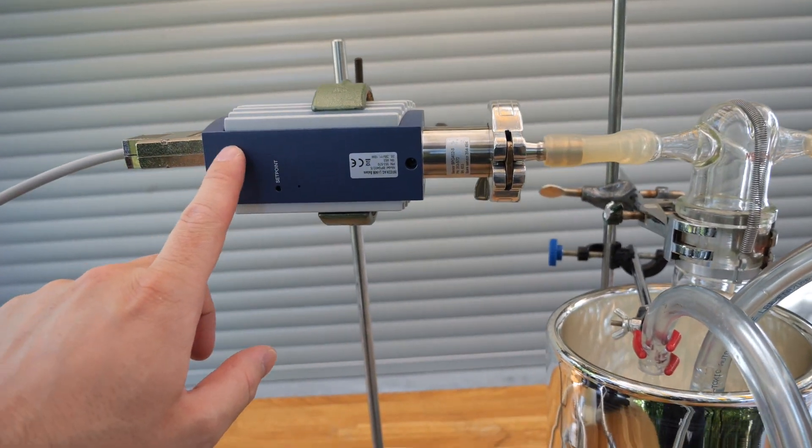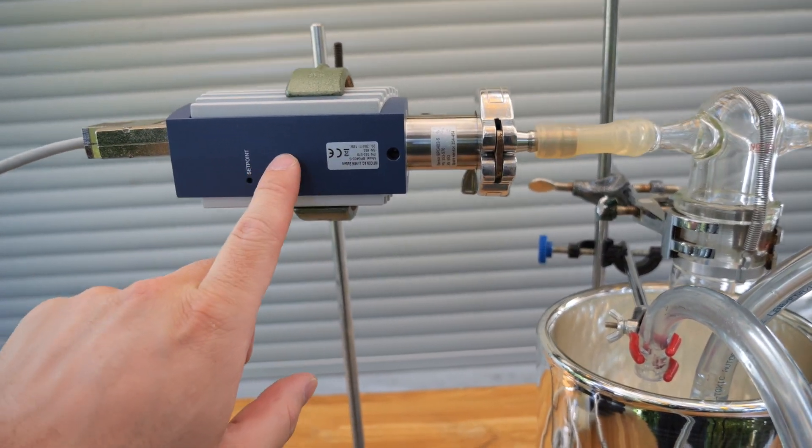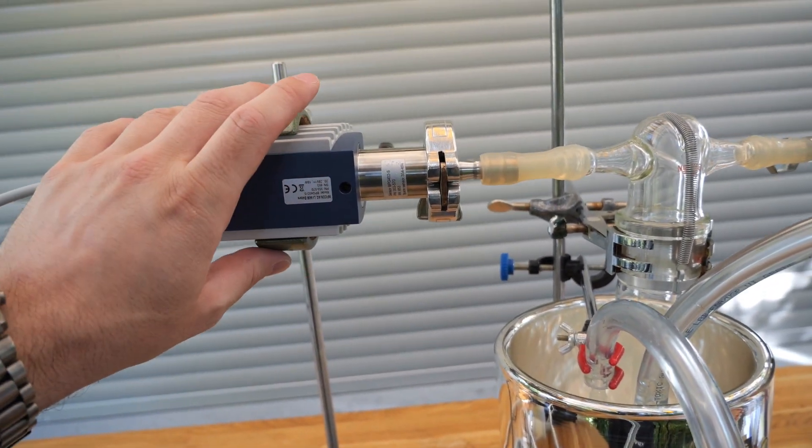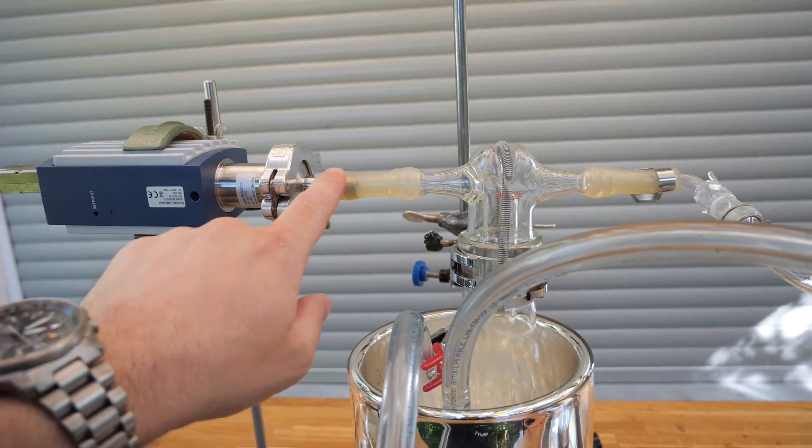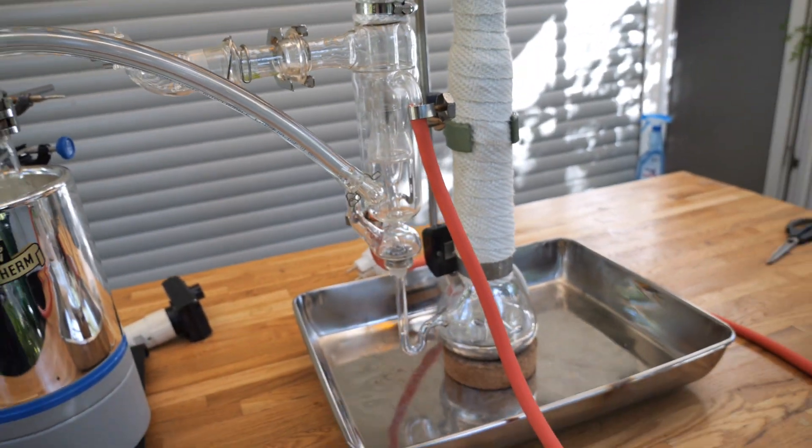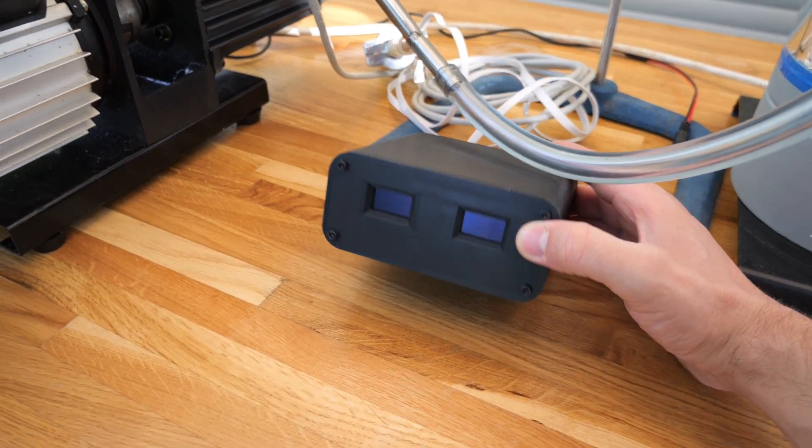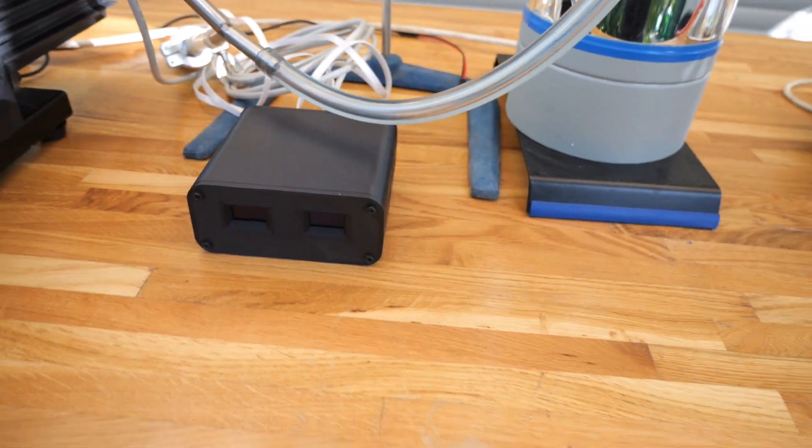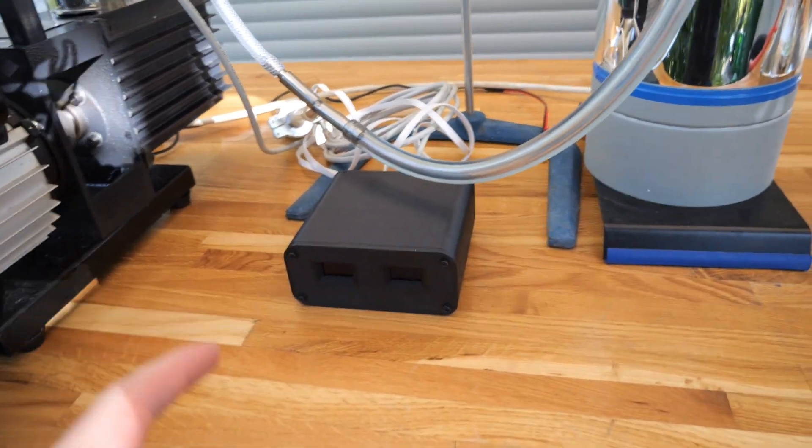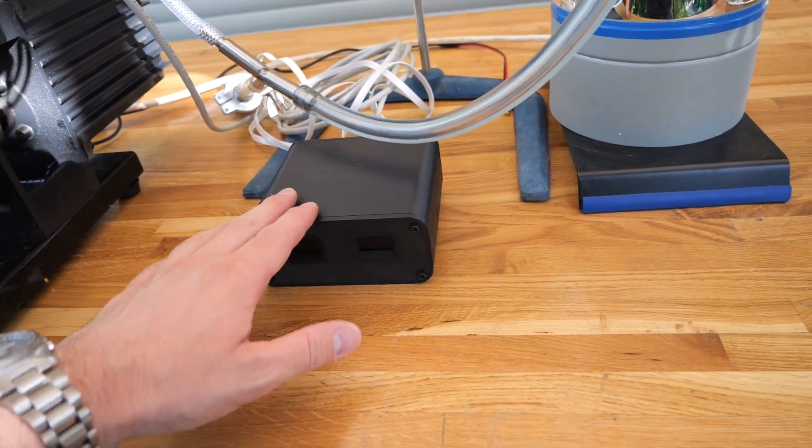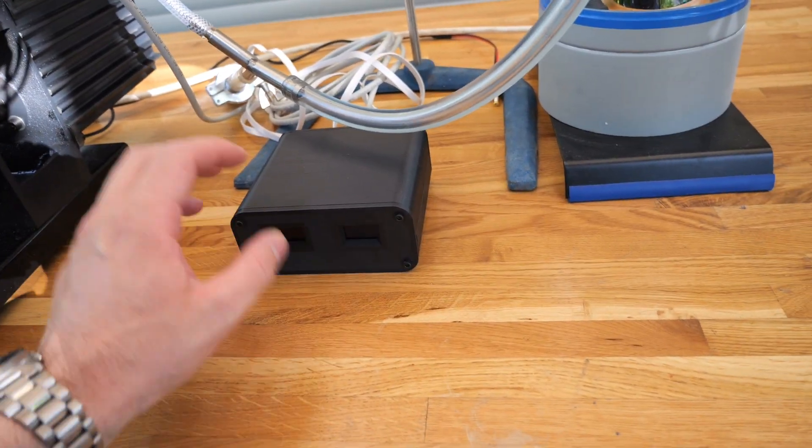In my case I have my Inficon BPG402 connected which is a high vacuum gauge and it will measure the pressure at this point here when we run the pump. Both vacuum gauges are connected to this guy right here. It is my new project, it is a vacuum gauge controller and this is just a small teaser. There will be a separate video about it.